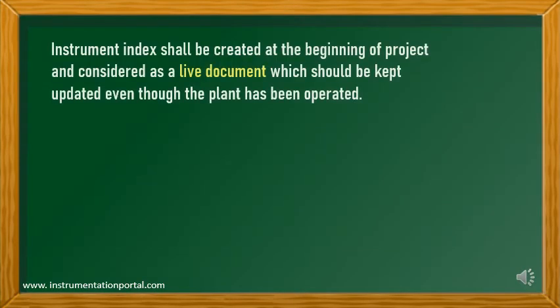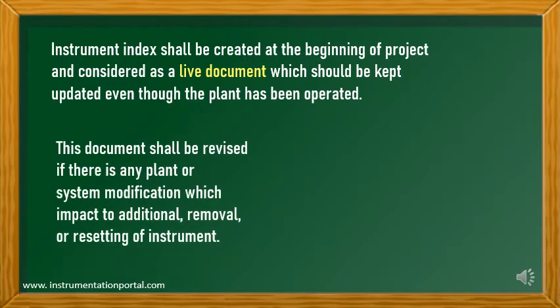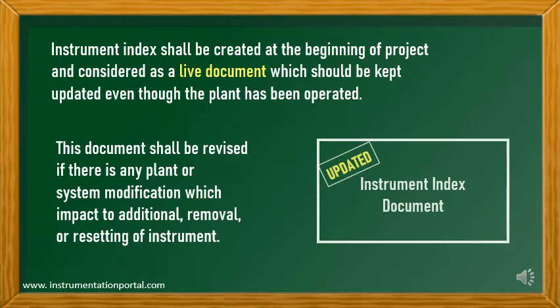Instrument index will be created at the beginning of a project and is considered a live document which should be kept updated even after the plant has been operated. The document shall be revised if there is any plant or system modification which impacts the addition, removal, or resetting of instruments.